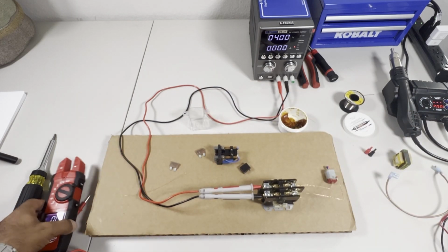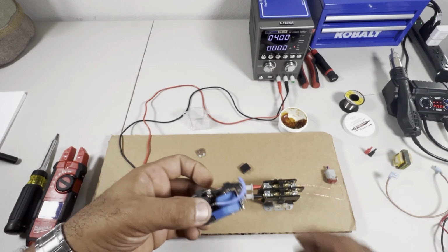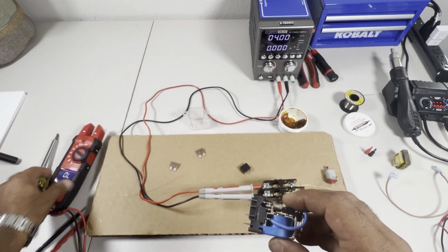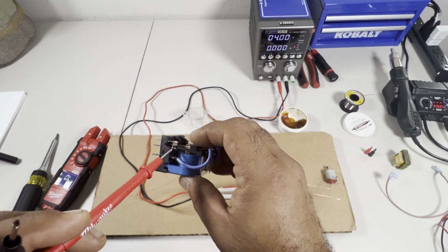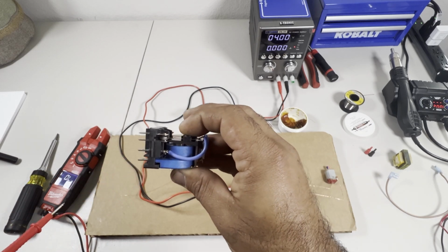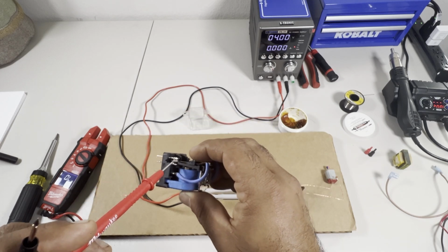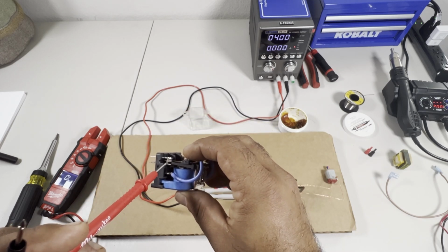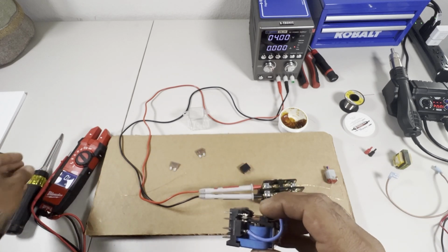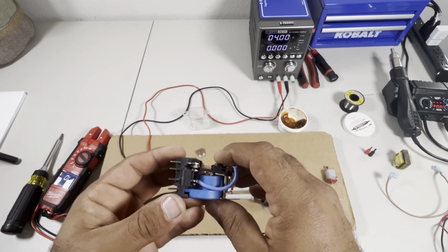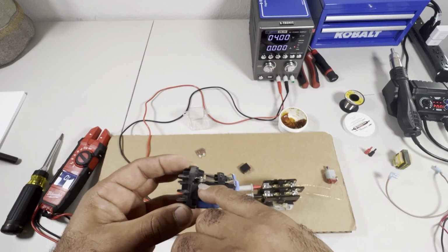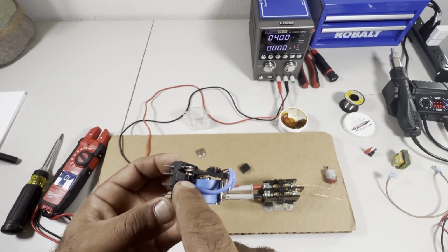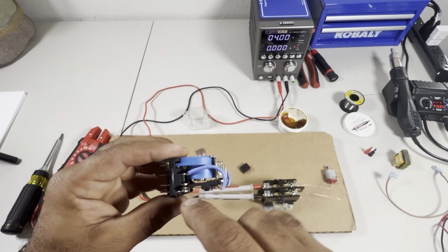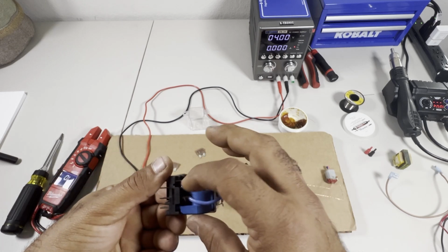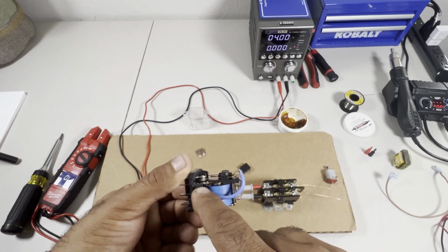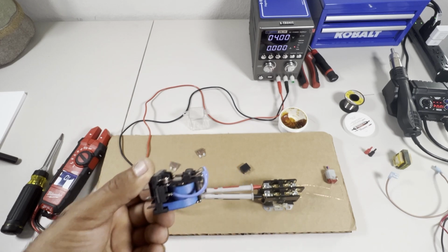Now, what happens when this relay goes bad? A lot of the time you're going to see that every time this relay opens and closes, there is going to be a small arc happening between these two points of contact every time. After a few years of usage, these arcs are going to cause oxidation right between those two points of contact. And the oxidation is going to cause the electrons that are trying to pass through to have a hard time passing through. They act like a resistance.